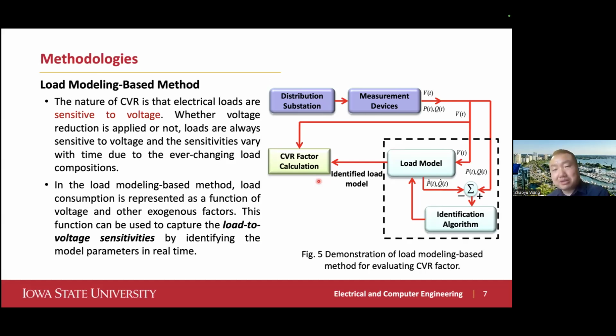Why? Because with constant power load, when you reduce the voltage, their current will go up. Their current going up means your line loss and transformer loss will go up. So the total consumption of the whole feeder will go up, and you'll have a negative CVR factor in this case.